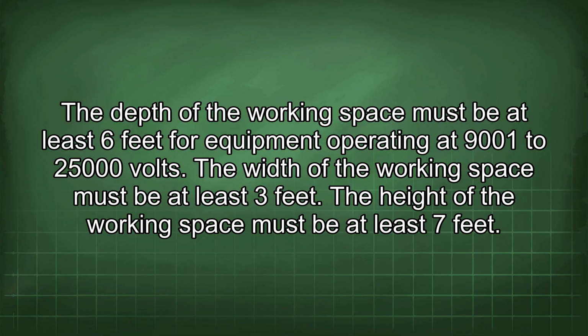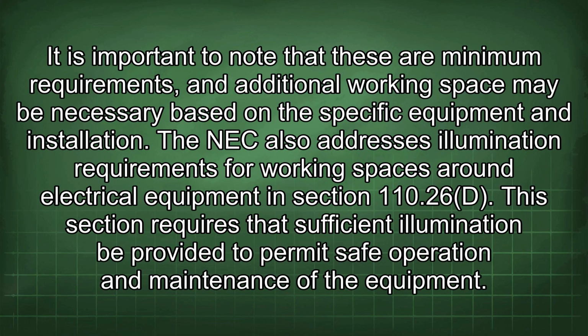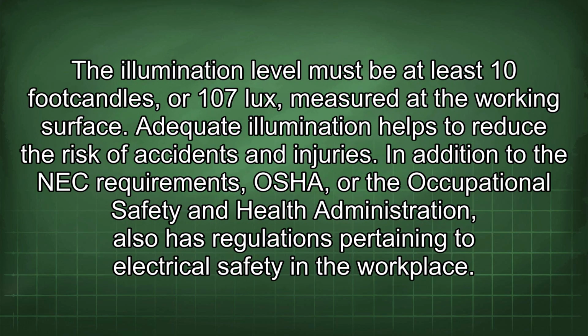The width of the working space must be at least 3 feet. The height of the working space must be at least 7 feet. It is important to note that these are minimum requirements, and additional working space may be necessary based on the specific equipment and installation. The NEC also addresses illumination requirements for working spaces around electrical equipment in Section 110.26(d). This section requires that sufficient illumination be provided to permit safe operation and maintenance of the equipment. The illumination level must be at least 10 footcandles, or 107 lux, measured at the working surface. Adequate illumination helps to reduce the risk of accidents and injuries.